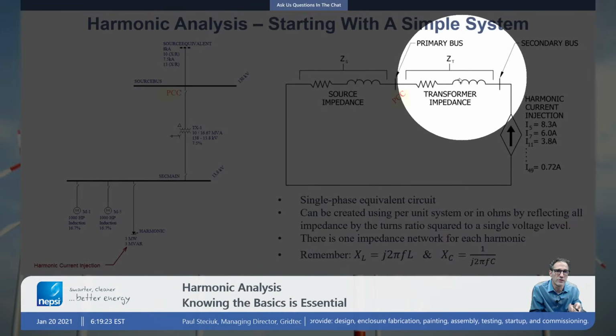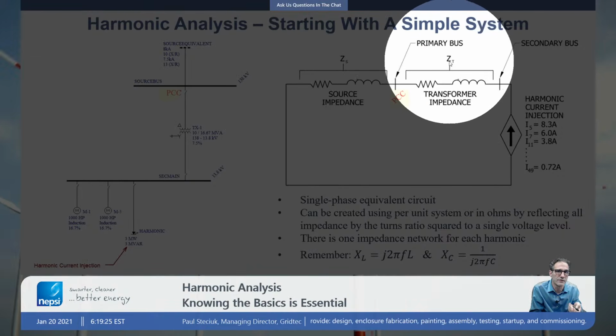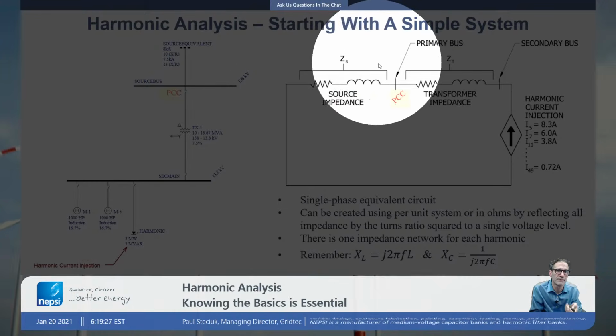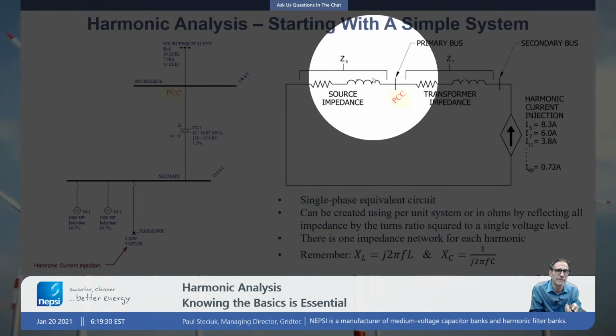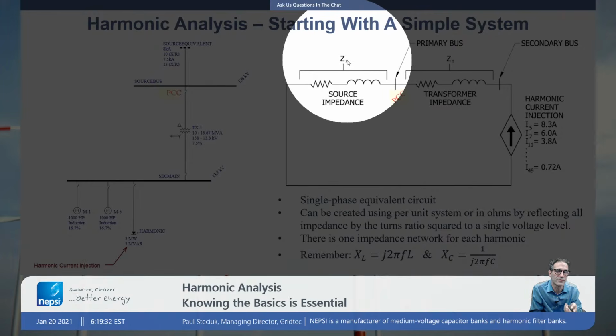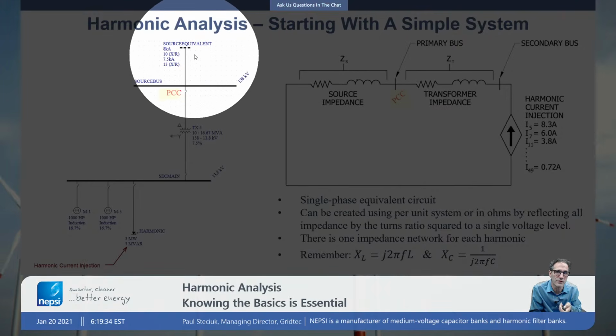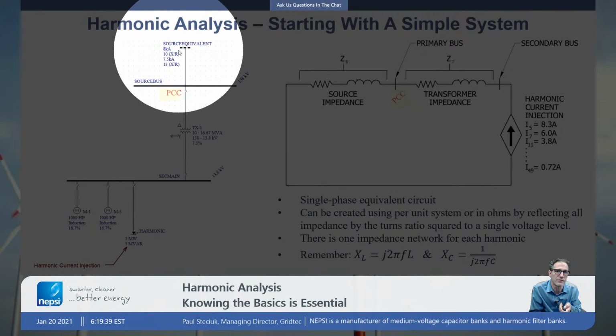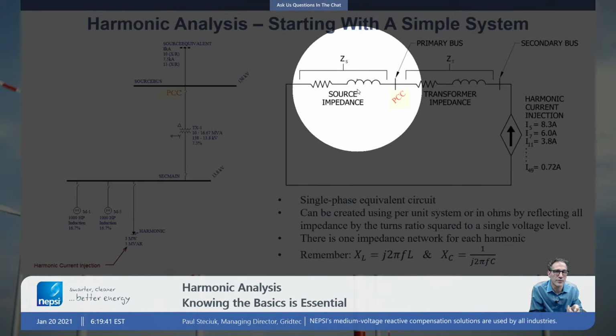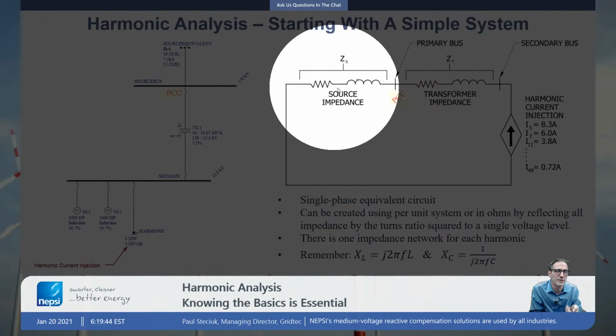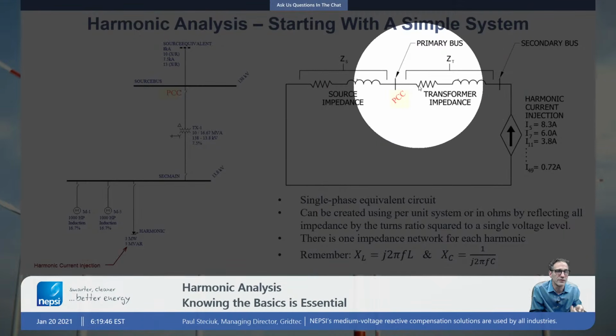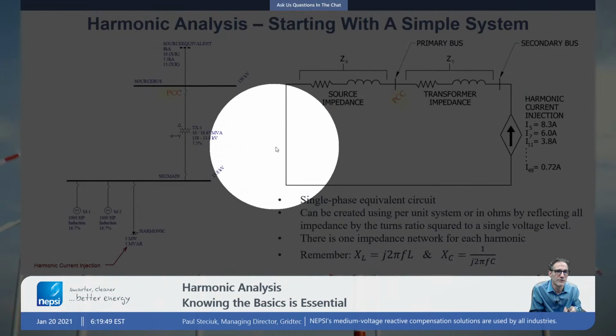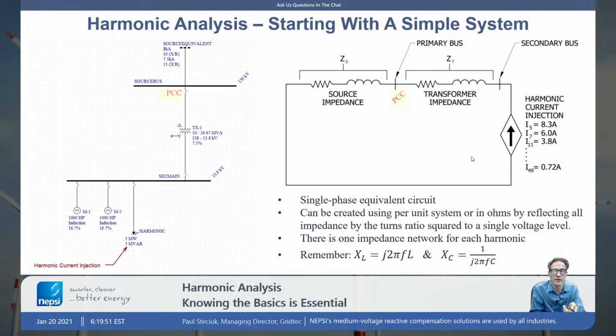So if we were to take this standard three-phase network shown on this one-line diagram, we could create an equivalent network over here consisting of Z T, which is a transformer impedance. It consists of both an X and an R. And then Z of S here, which is a source impedance. It represents the source impedance from the utility based on the short circuit impedance of the network. And that again is represented by the X and the R value here. So in total we have two series impedances here. It's a very simple network. And so remember what we did here, we've taken a three-phase network and we converted it to a single-phase model, and that's what we show here.